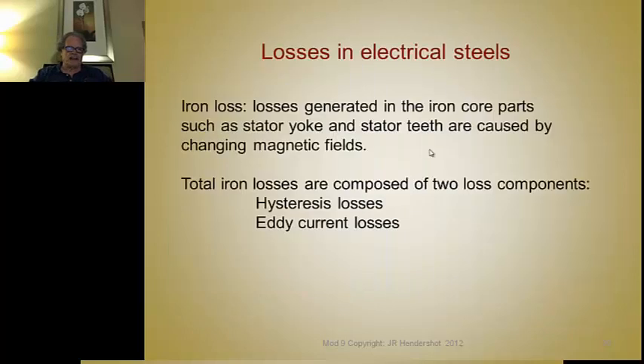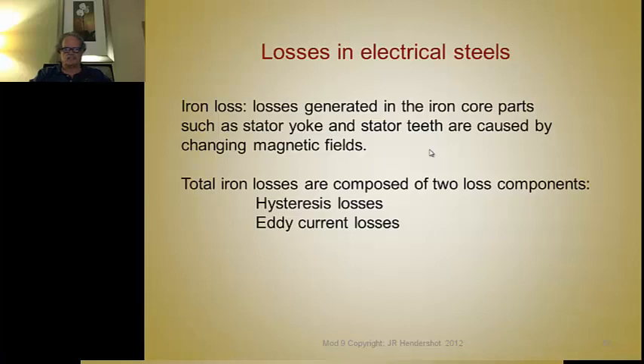When you magnetize it, you magnetize in the same direction as it was oriented to get the maximum energy product possible. Now, we still need to talk about losses in electrical steels. The losses in magnets and steels are caused by dB/dt — the time rate of change of magnetic fields — which causes eddy currents and losses.